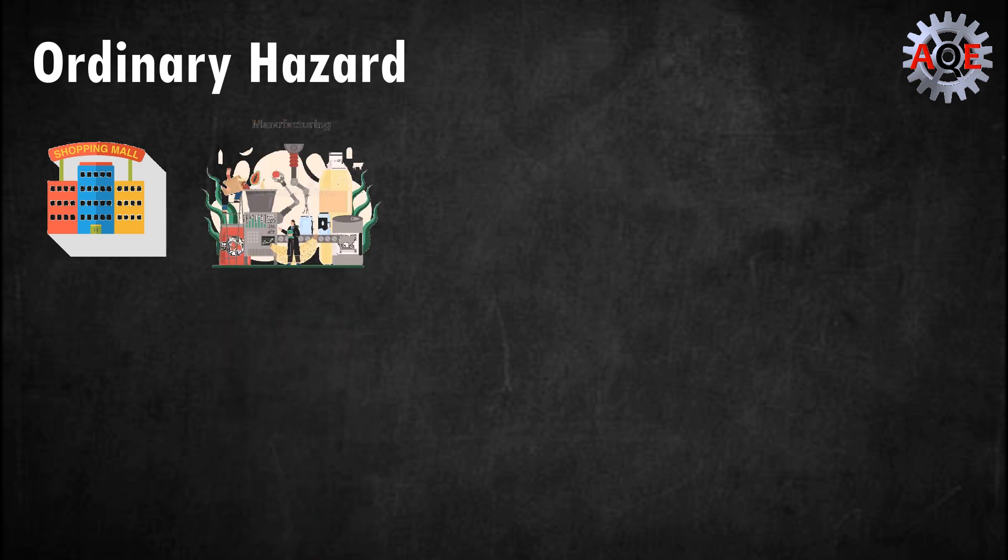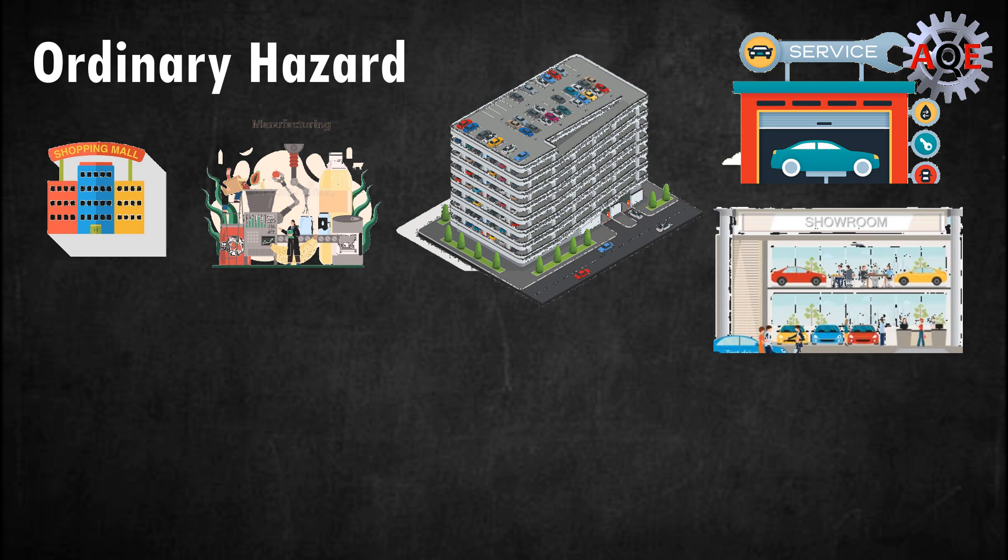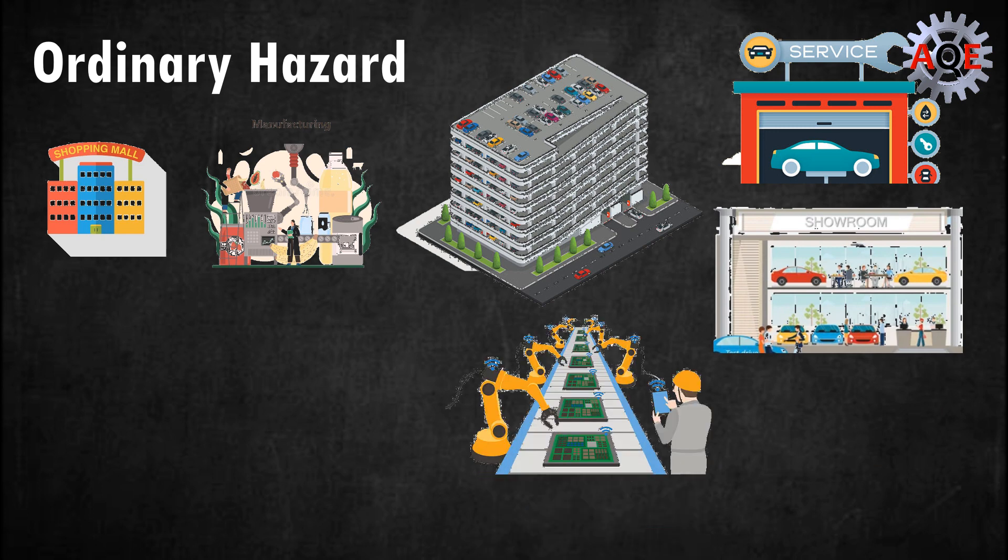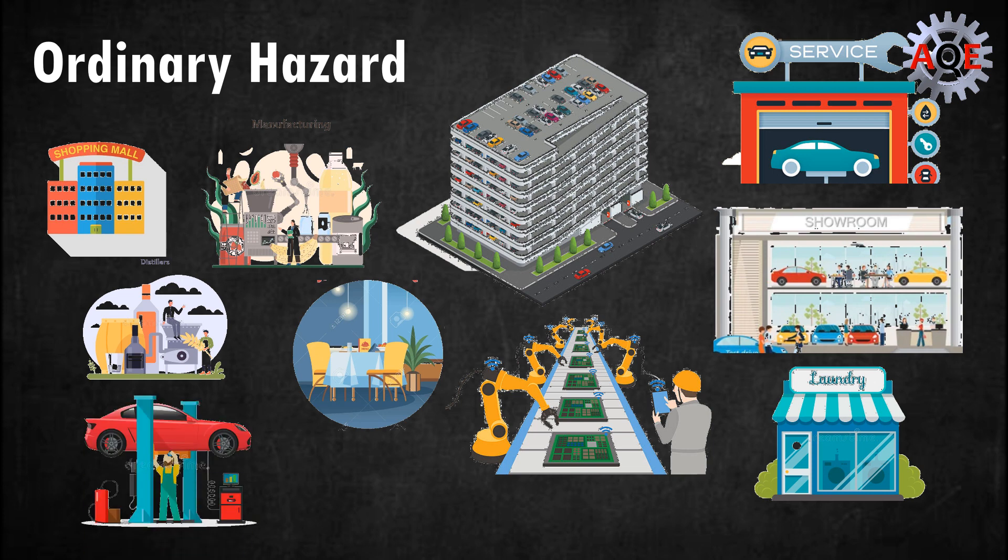Some businesses and environments that constitute an ordinary hazard are malls, light manufacturing or research operations, parking garages, workshops, automobile showrooms, electronics plants, laundries, restaurant service areas, drink manufacturing or maintenance service areas.